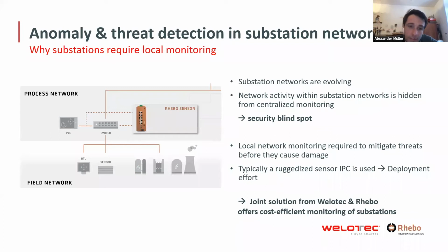So we should not treat a substation network anymore as secure-by-design because it has no access from the outside world. When we want to know what's going on within the substation network, it's not sufficient anymore to go with the centralized approach I described before, because at the control room we will only see what is happening within the substation once it has an impact on the process itself, meaning the power generation or power transmission process.